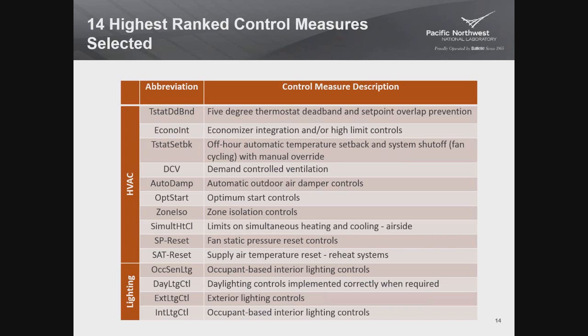On to lighting. Occupant sensor control, those I'm sure you're all familiar with. We looked at one. People come into a room, the lights turn on, or maybe they're manual on in some code requirements. They can't turn on automatically. But the key is that when people leave a room, they shut off. Daylighting controls: if you have spaces that have ambient light introduced from windows or skylights, and there's enough light that you don't need the electric lighting, these controls include a photo sensor and a controller that dim the electric lighting so that you only get what you need and save some energy there.